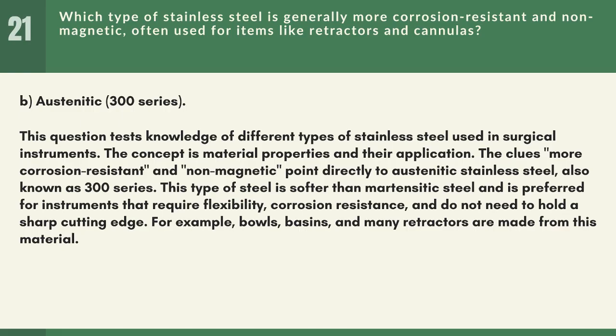This question tests knowledge of different types of stainless steel used in surgical instruments. The concept is material properties and their application. The clues, more corrosion-resistant and non-magnetic, point directly to austenitic stainless steel, also known as 300 series. This type of steel is softer than martensitic steel and is preferred for instruments that require flexibility, corrosion resistance, and do not need to hold a sharp cutting edge. For example, bowls, basins, and many retractors are made from this material.